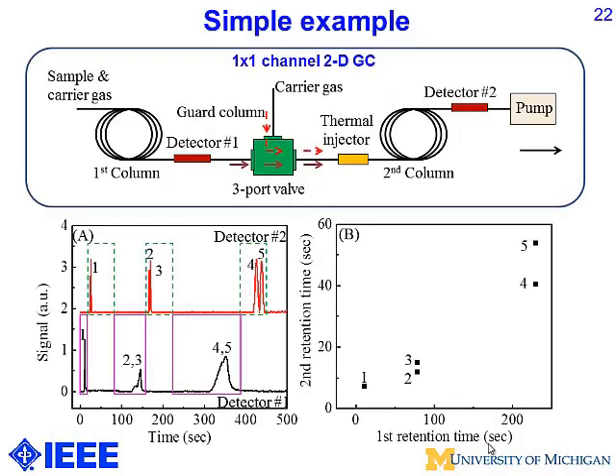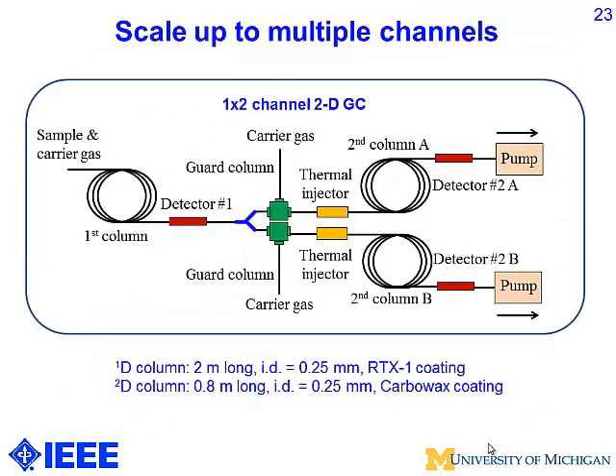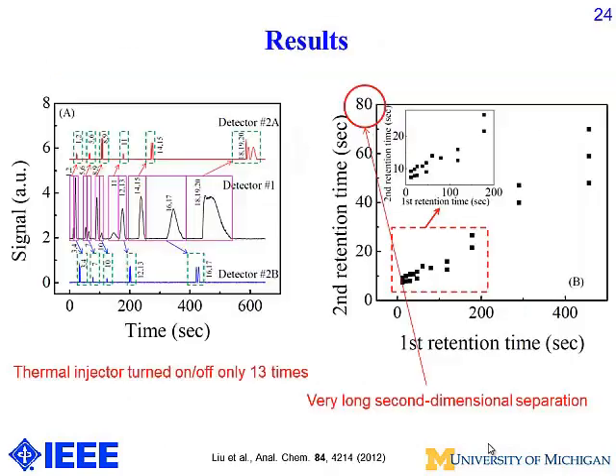Here's the simplest implementation: we have a first-dimensional and second-dimensional column, with a detector after the first-dimensional separation and another after the second. In an example with five analytes grouping into three co-eluted peaks, we send each peak to the second-dimensional separation where they are well separated. In a one-by-two channel configuration, co-eluted peaks are sent alternately to upper and lower channels. The 2D chromatograms show second-dimensional separation up to about 80 seconds — something that cannot be done with conventional 2D GC where the second separation must finish within five to ten seconds.